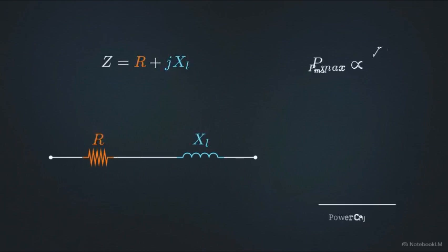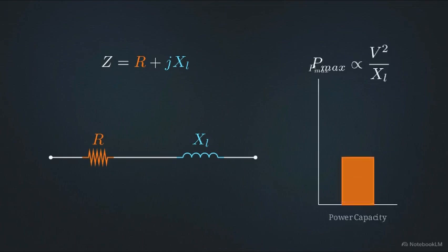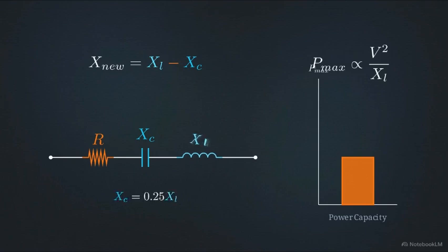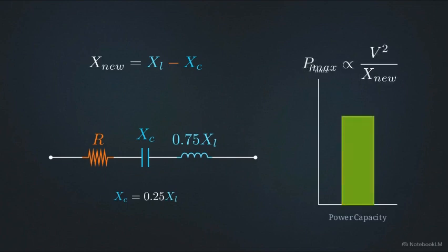This schematic shows a transmission line's baseline impedance. Instead of increasing the voltage, engineers can manipulate the denominator of the power equation by inserting series capacitive compensation directly into the circuit. The inserted capacitive reactance creates a direct mathematical subtraction against a line's natural inductive reactance, lowering the total impedance. Applying a 25% compensation drops the effective line reactance down to 3/4 of its original value. Shrinking the denominator proportionally scales up the total power the line can safely carry.